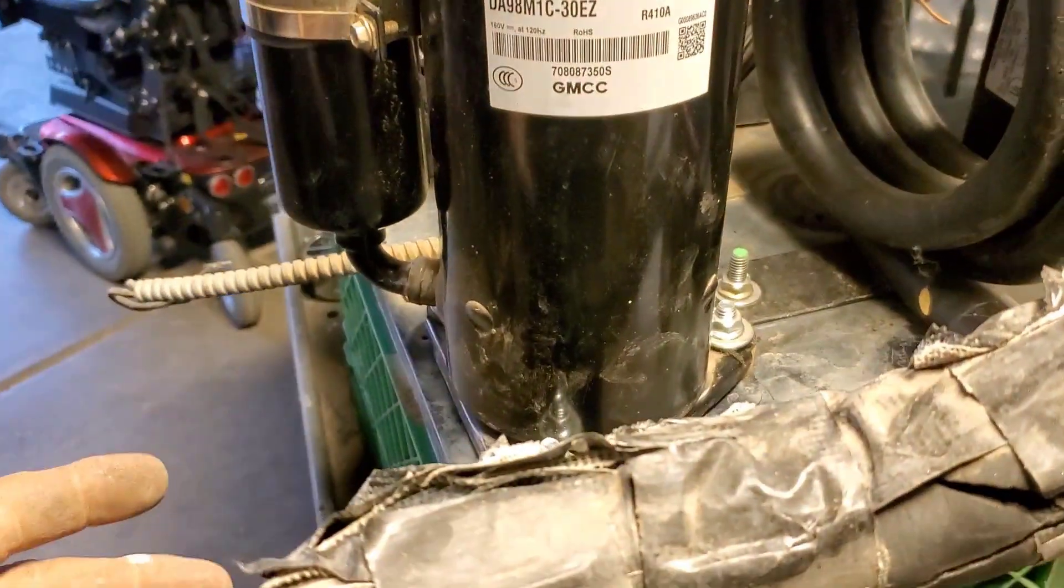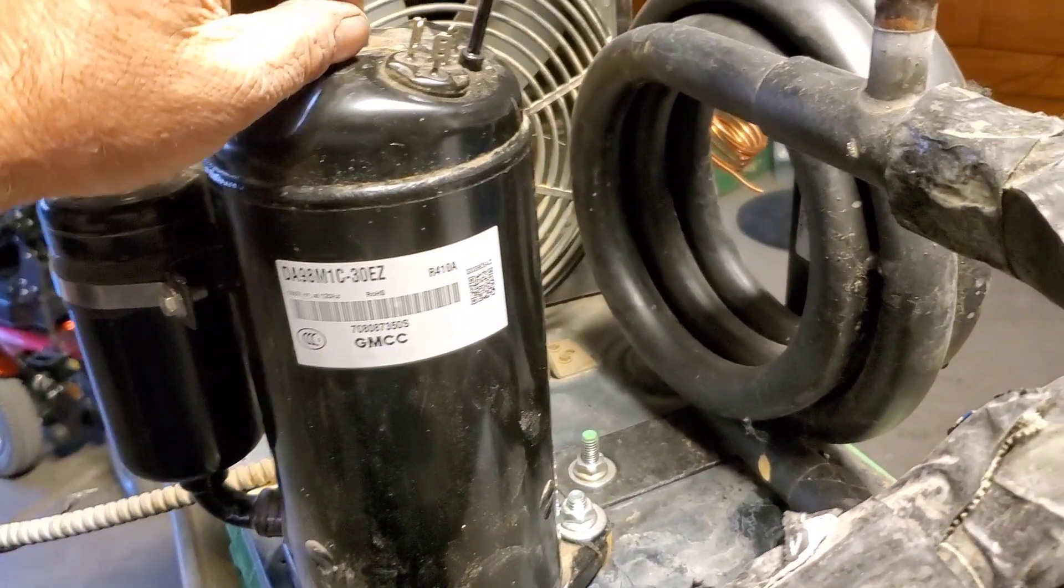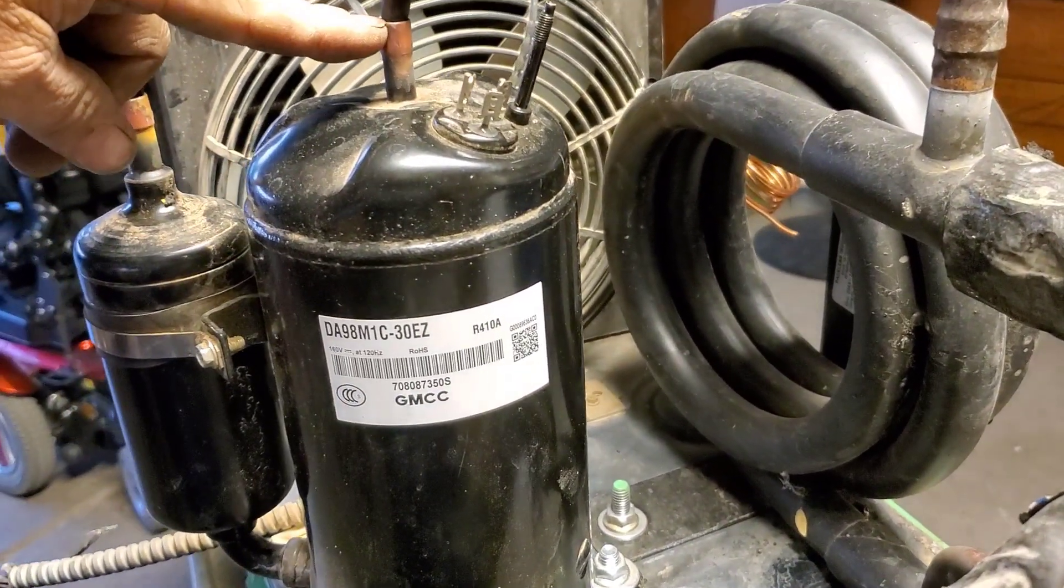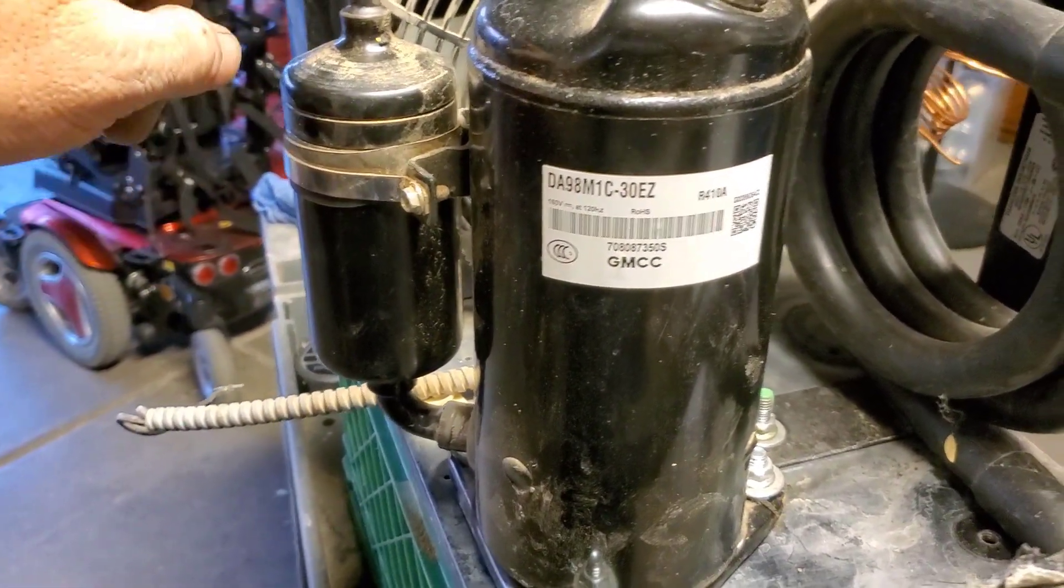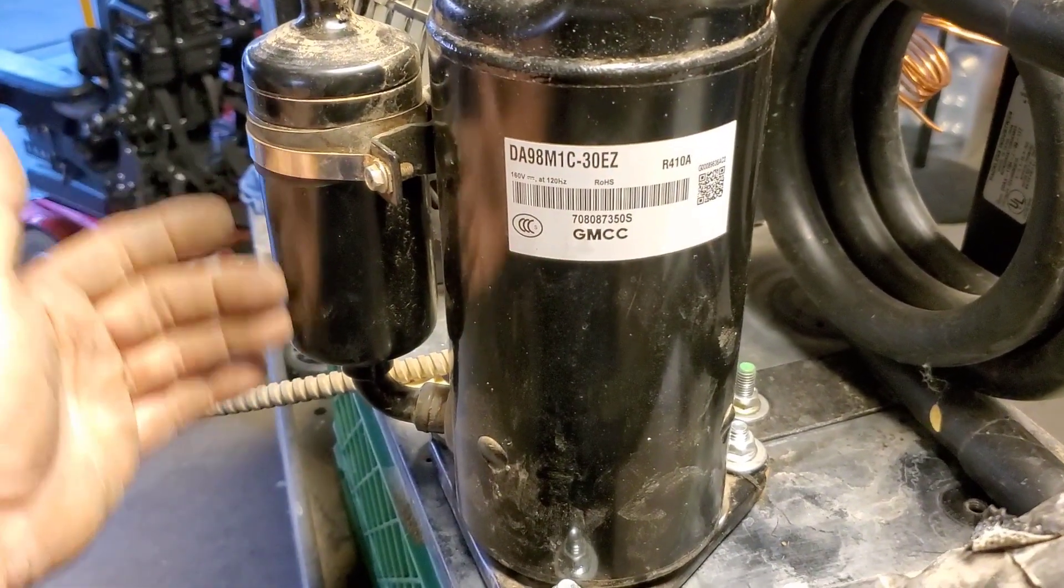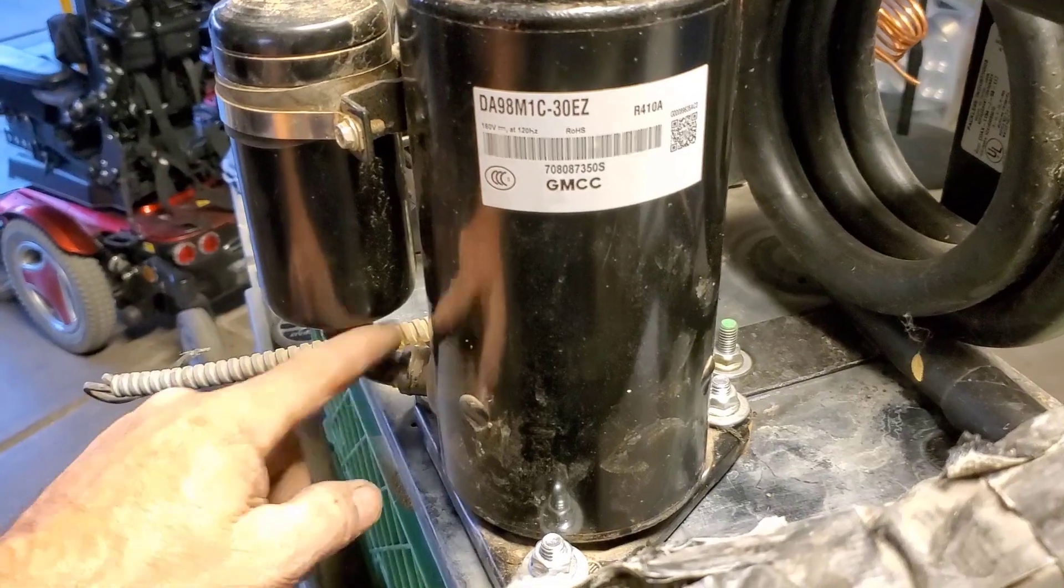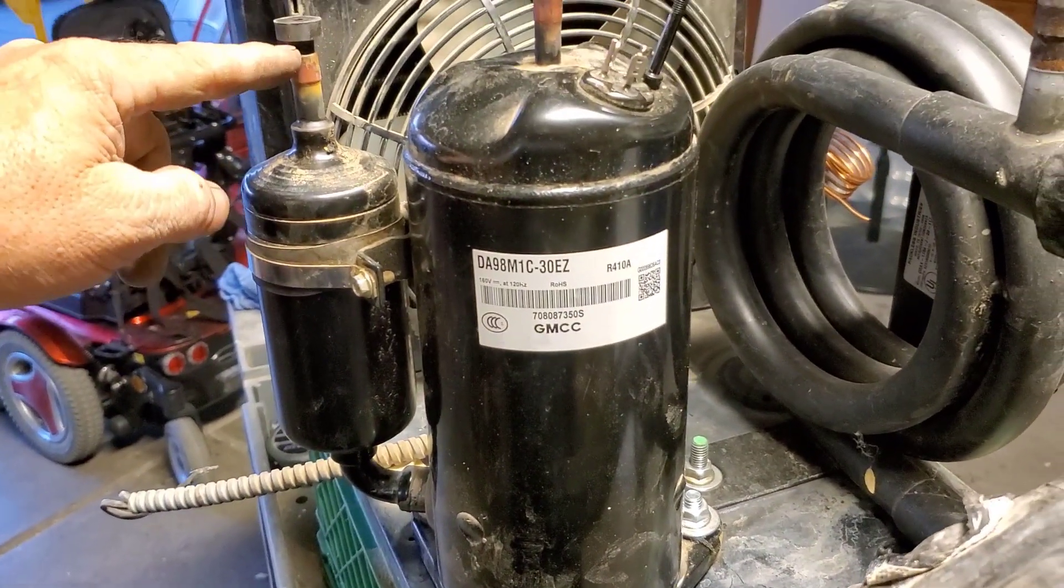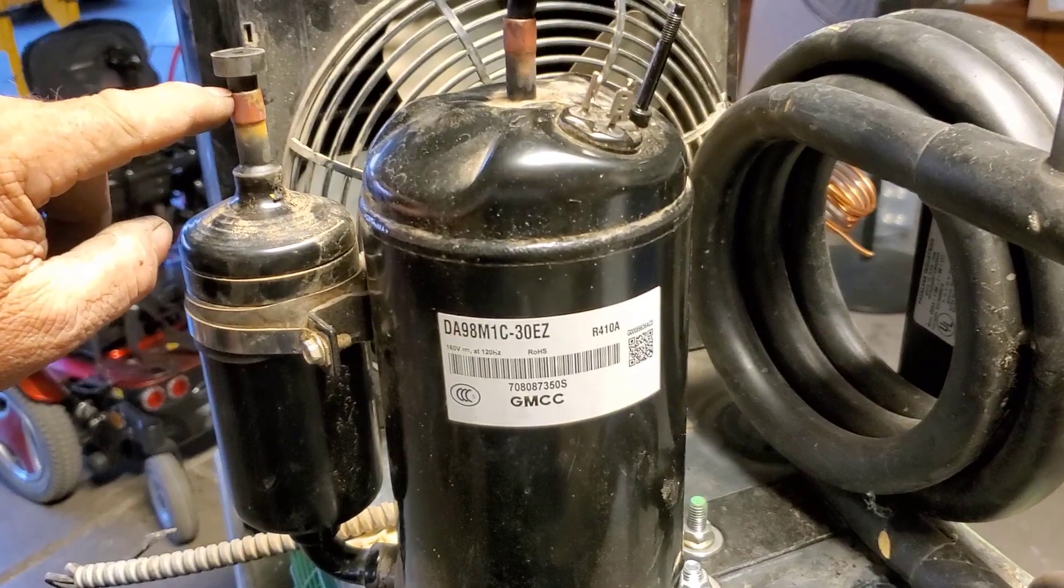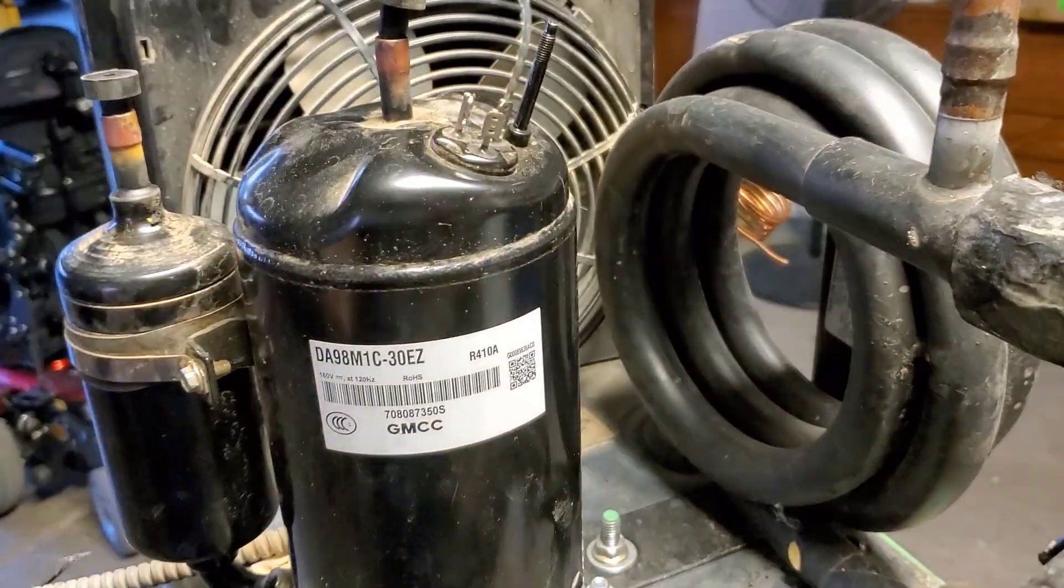Nice bell end right there. That'll go like that. And then this is three-eighths, I gotta step it down to five-sixteenths which is coming out of the top of the rotary compressor. Now people look at these and think this is the suction, but it's not—this is the discharge. This is the built-in accumulator and strainer that comes on these things. And then you've got your suction, so suction's only three-eighths on this, five-sixteenths discharge.